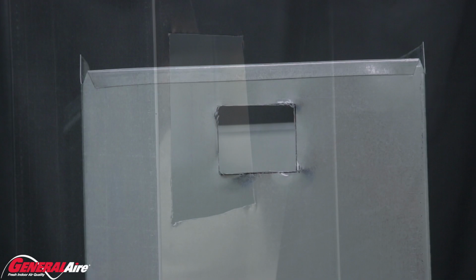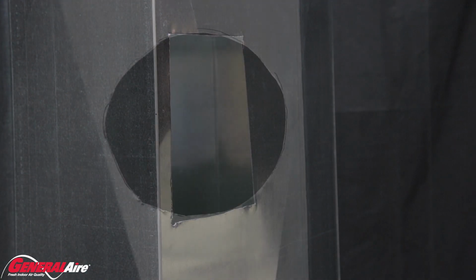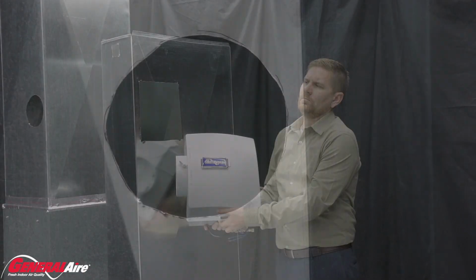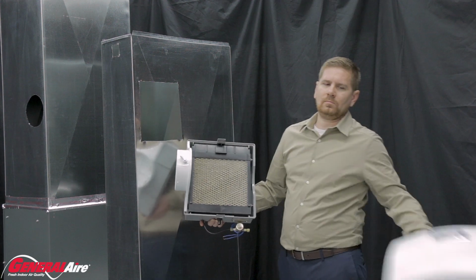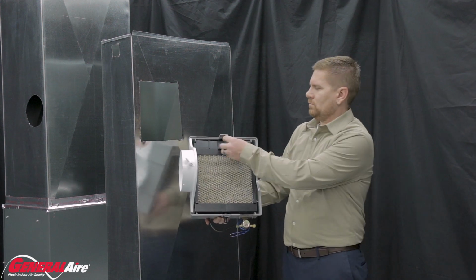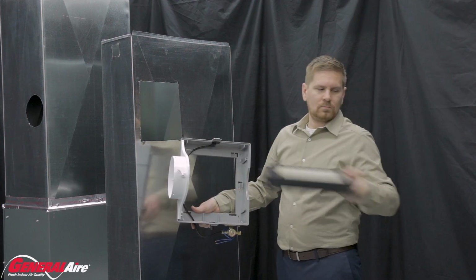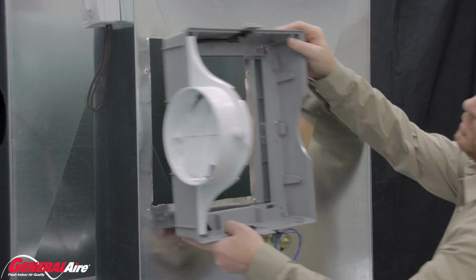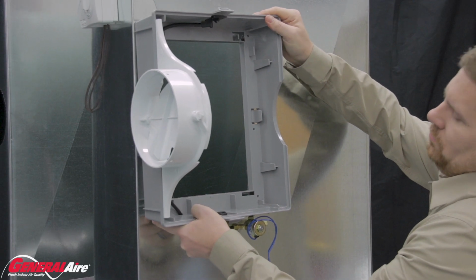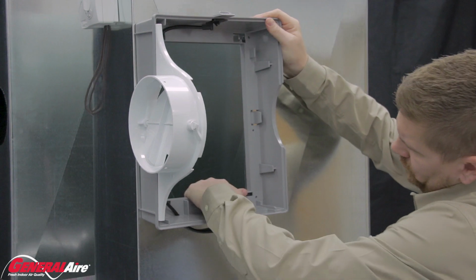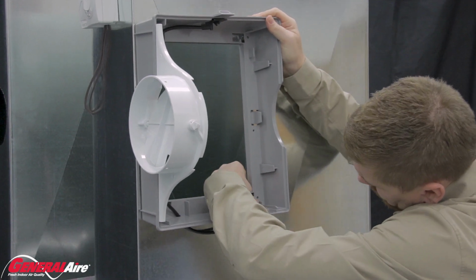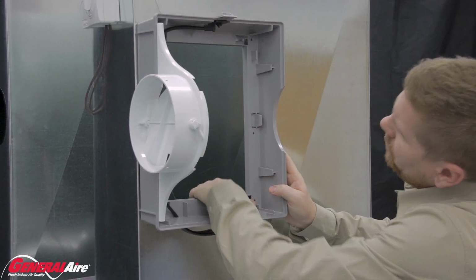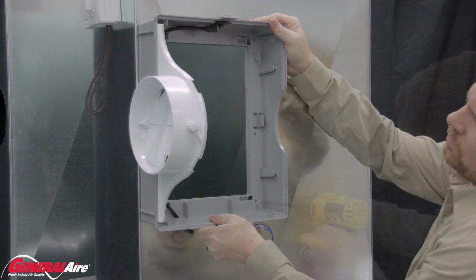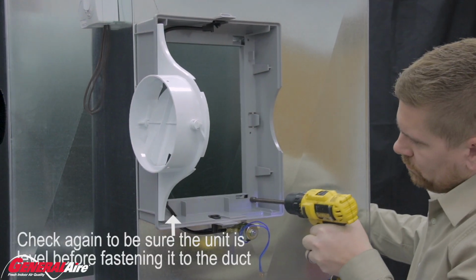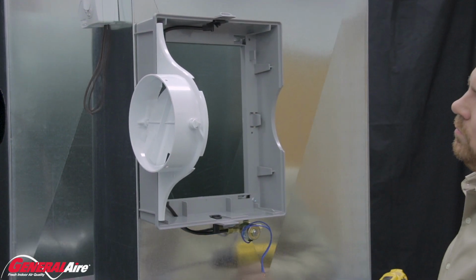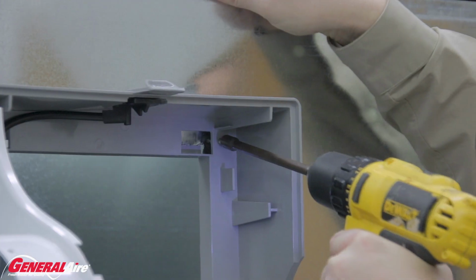Now that all 3 holes have been cut out of the duct, it's time to first install the humidifier. Separate the 900M cover and vapor pad frame from the chassis. Place the chassis on your humidifier cutout. To secure the humidifier, slide the unit onto the upper tabs first. Lower it onto the bottom tabs. It's now locked in place. Use sheet metal screws to secure the base to the ductwork, utilizing the holes in the base.